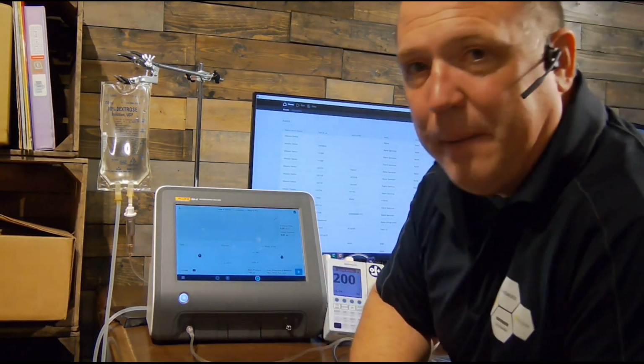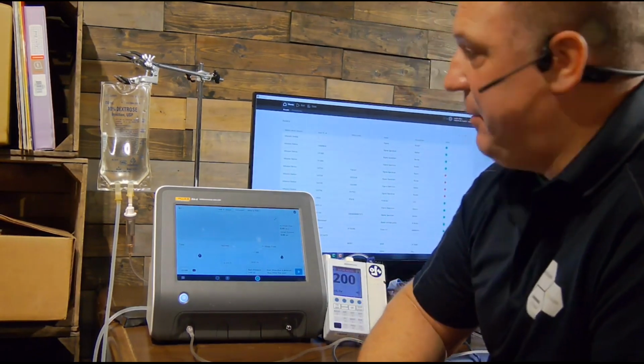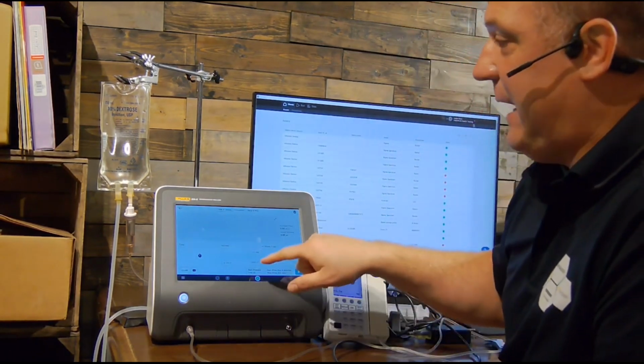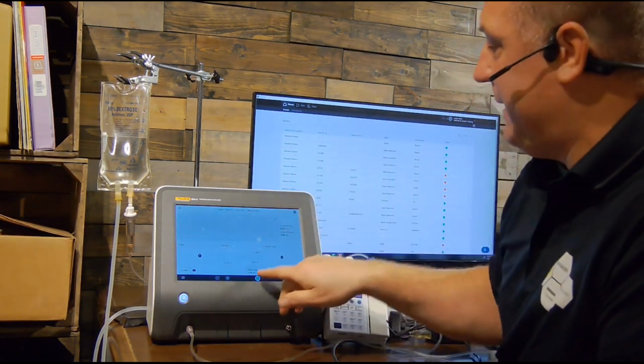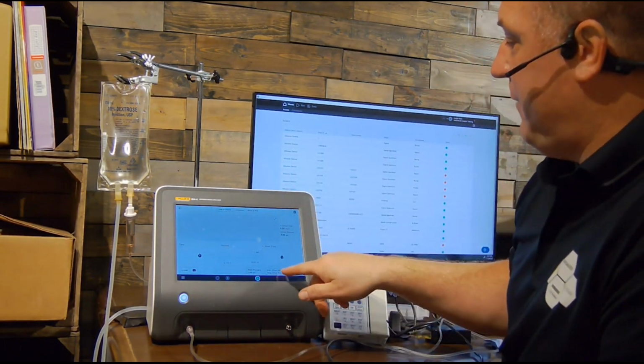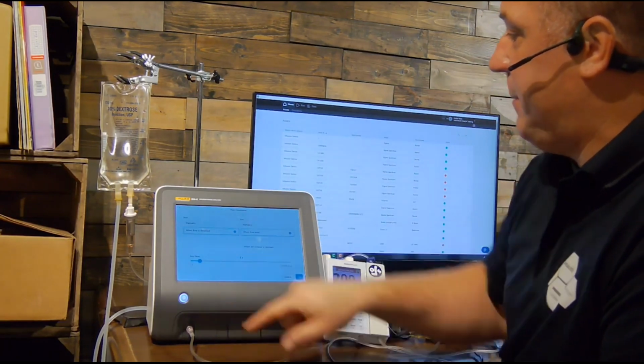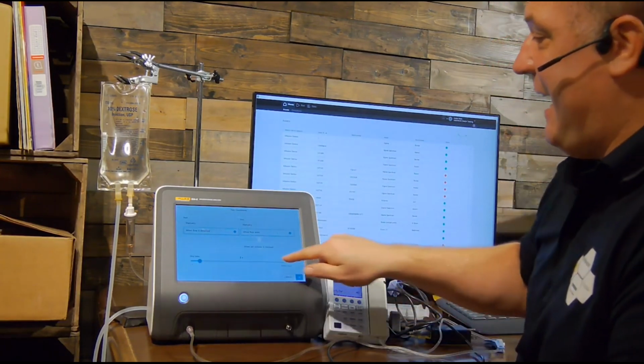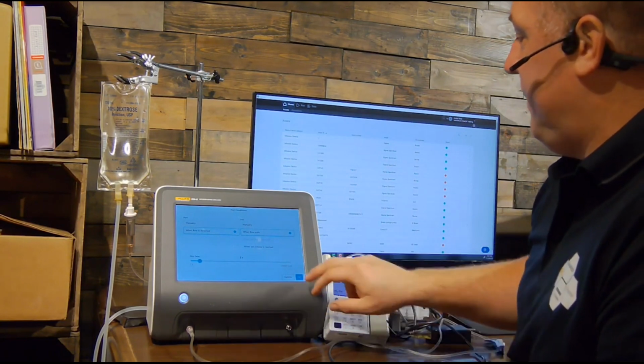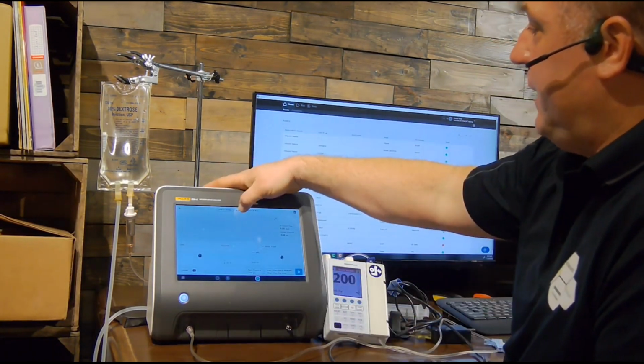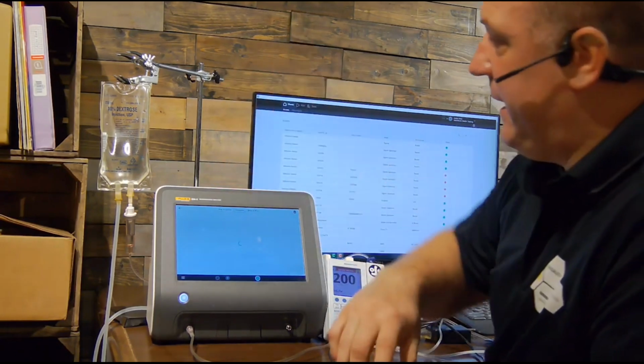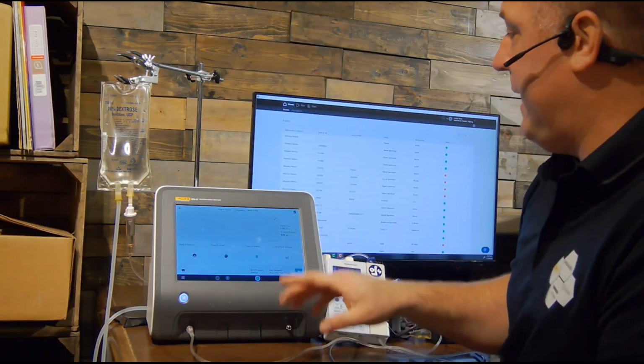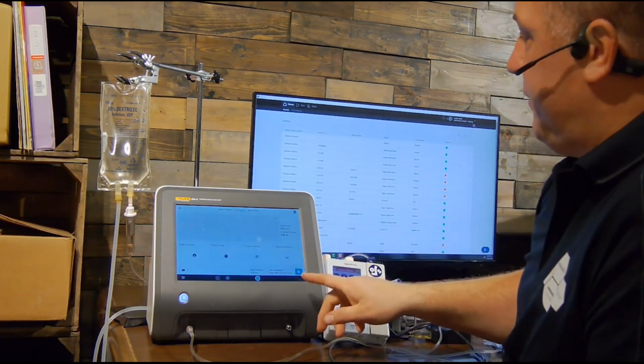I can introduce back pressure. So if I'm an OEM and I'm doing some testing on this, or I have some specific tests where I want to sense a back pressure, I can add back pressure to it. When is my IV pump going to start and stop? All that can be programmed into here. That delay can be extended out for when it stops. All that's there. Here's my occlusion screen. We saw that in the automatic mode and all of its features.